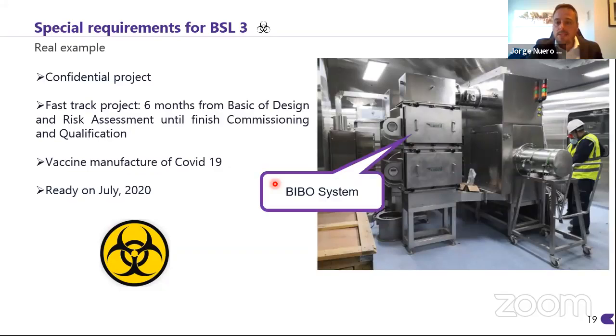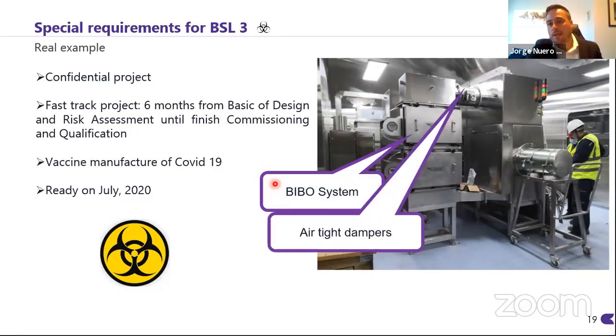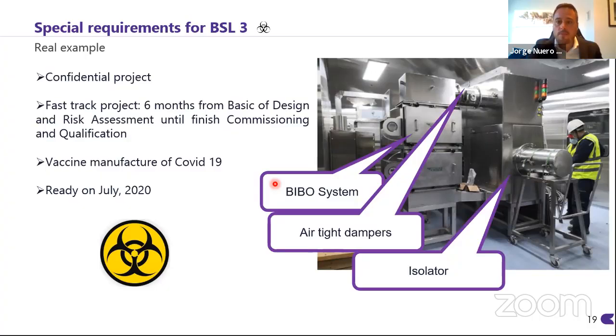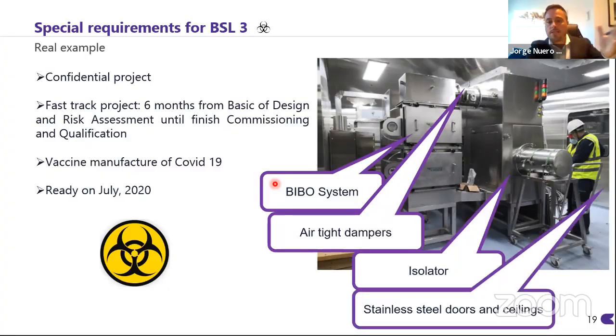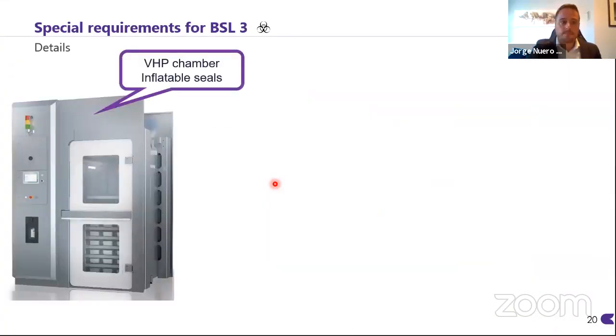So you can see here during the installation, this is the bag-in, bag-out filter, the airtight dampers. This is an isolator manufactured by AUSTAR as well. And in this case, because we did the decontamination of the room, all the walls and ceilings and doors and so on are manufactured in stainless steel to perform the VHP decontamination. It is not needed, to be honest, because VHP is not very aggressive to our standard clean room material, but this was requested by the customer in this case. Here you can see some details of the installation, like this VHP chamber equipped with inflatable seals. This is from Steris.